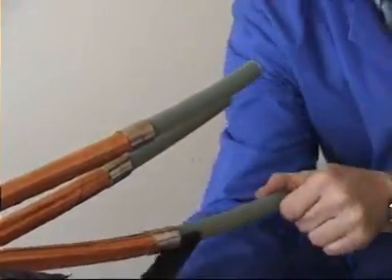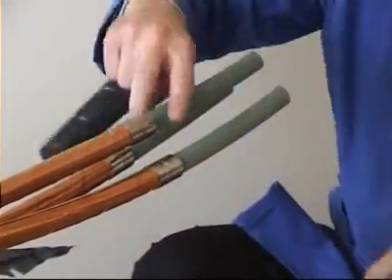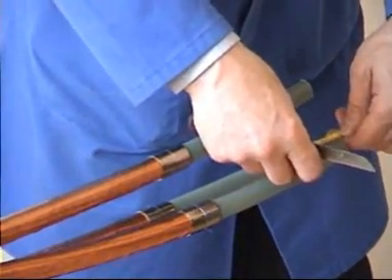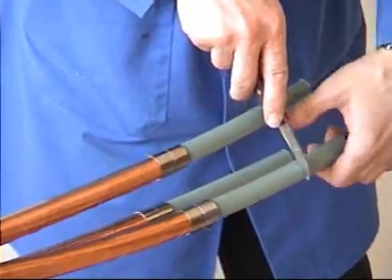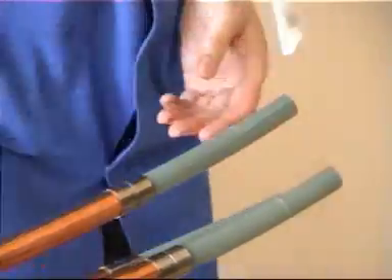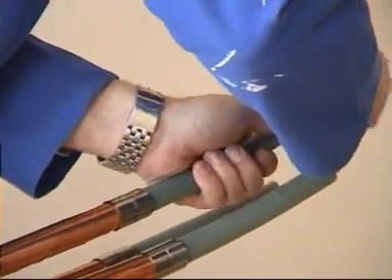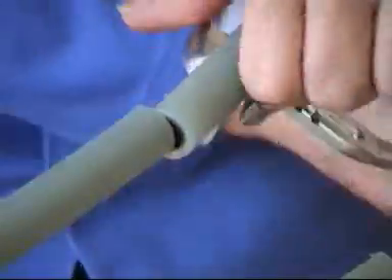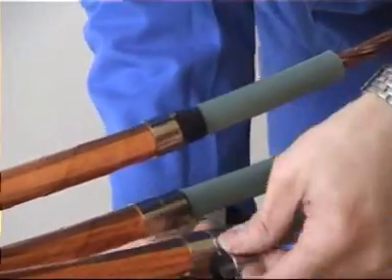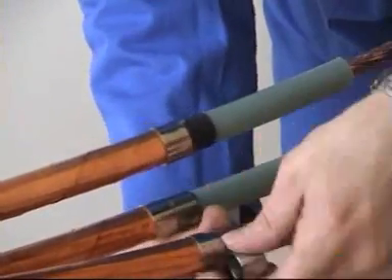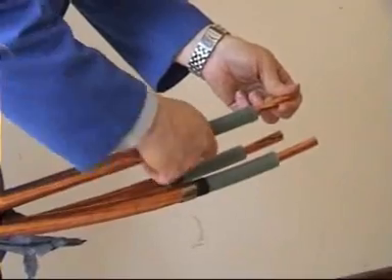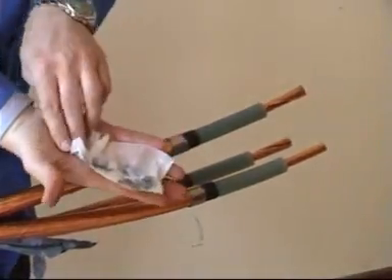Repeat this on the remaining cores. According to the length of the connector, mark out the insulation and remove, ready to fit the connectors at a later stage. Remove the roll springs that help to achieve the screen cut and with cable tissues wipe off any remaining residue from the primary insulation.